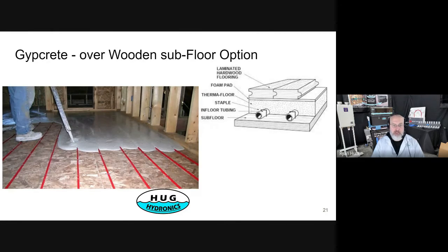You staple the tube down to the floor, and then you've got to plan 1.5 inches thickness to be able to fill that with a 1.5 inch layer of gypcrete. So you've got a different bottom plate, an additional bottom plate under the wall, and that allows for that thickness. And then you've still got a bottom plate to attach your drywall to and such. This has the advantage of making the floor feel more solid. It's more sound insulating between upstairs and downstairs, and it's a moderate price. Sometimes it's tricky to find a good contractor, though.